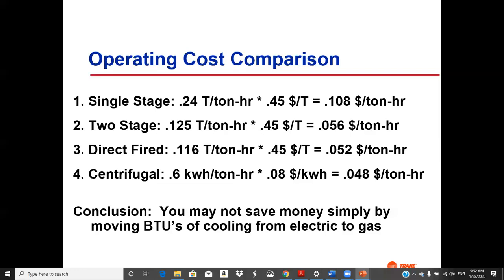And then we're going to put in a different chiller type. We've got a water-cooled centrifugal in it, and you're going to go to an air-cooled scroll type. So these are different types of water chillers that are on the market. An air-cooled will not be as efficient as a water-cooled. So the chiller will be less efficient, but you do lose a cooling tower, because if it's air-cooled, you don't need a cooling tower.